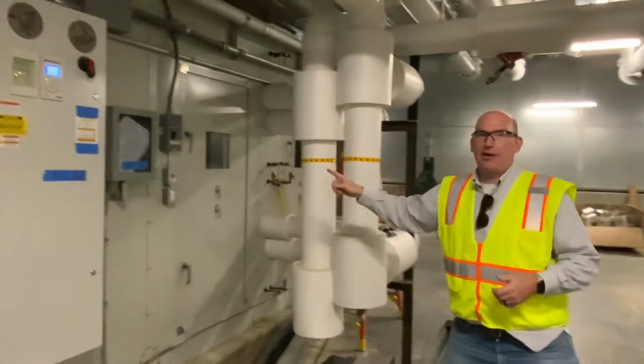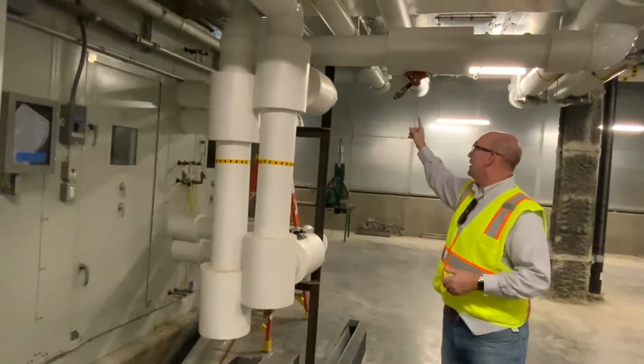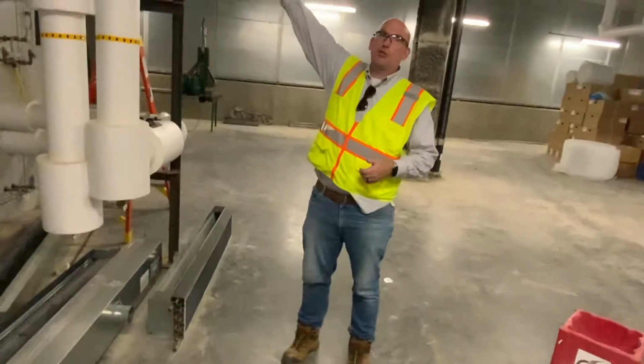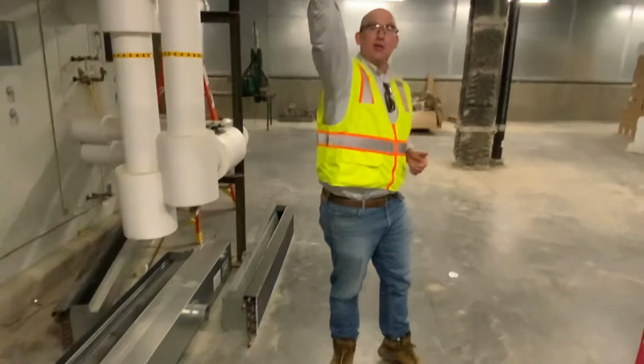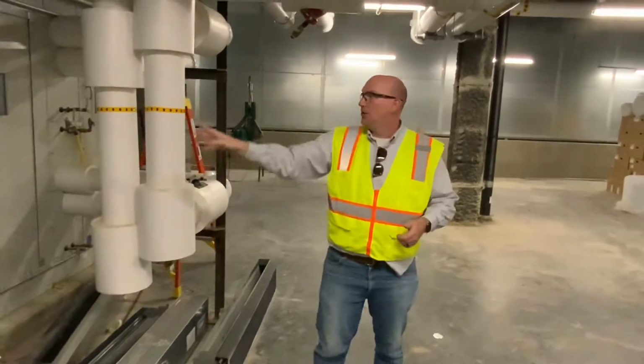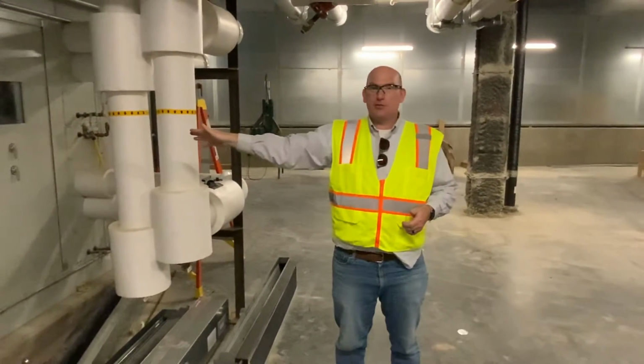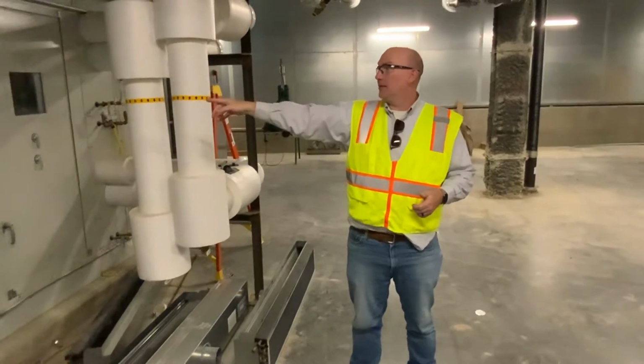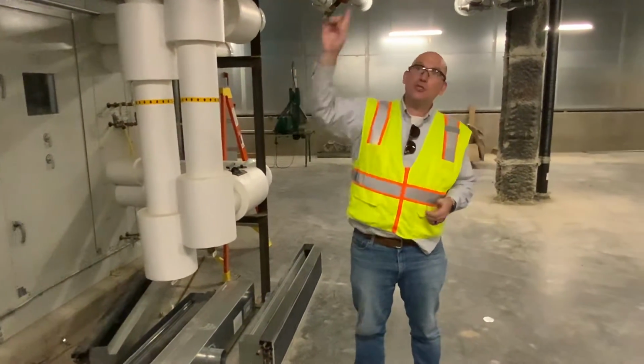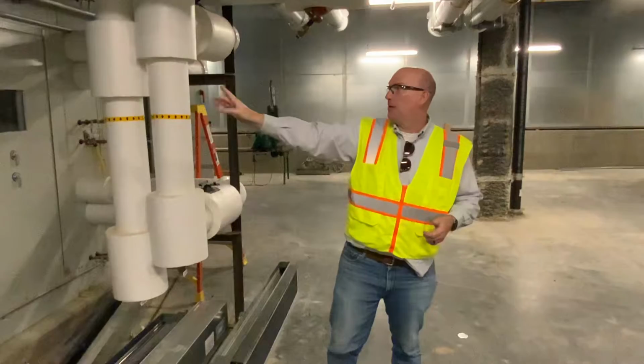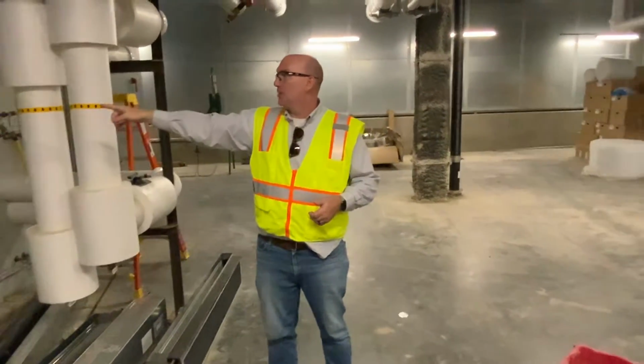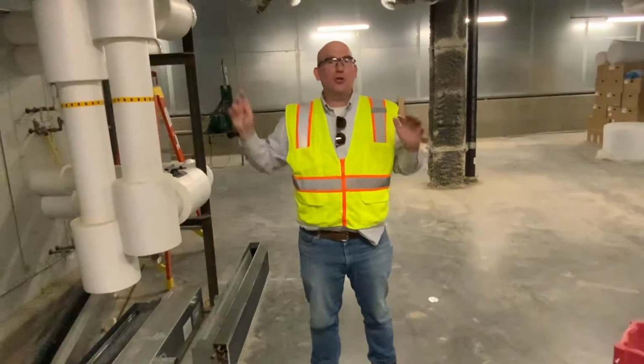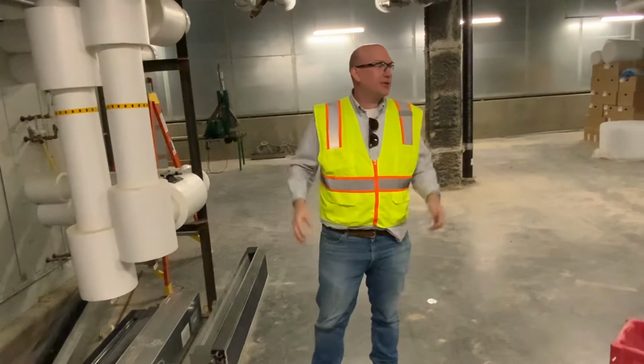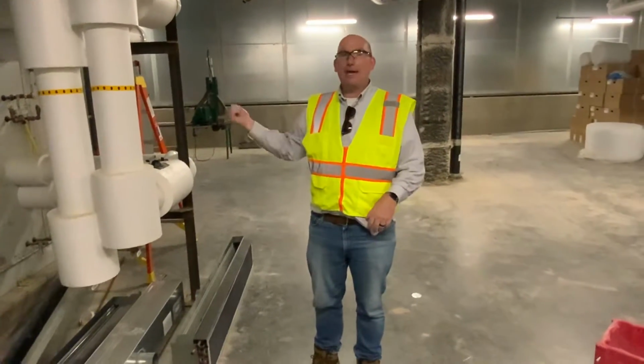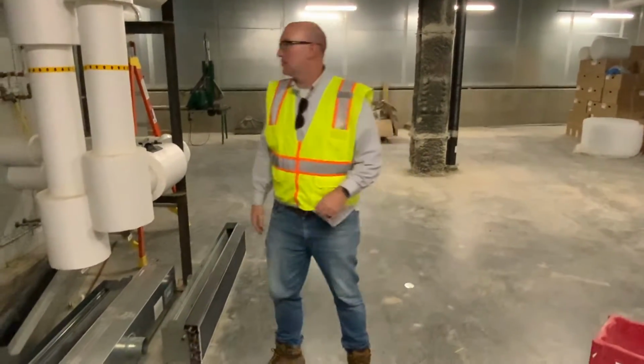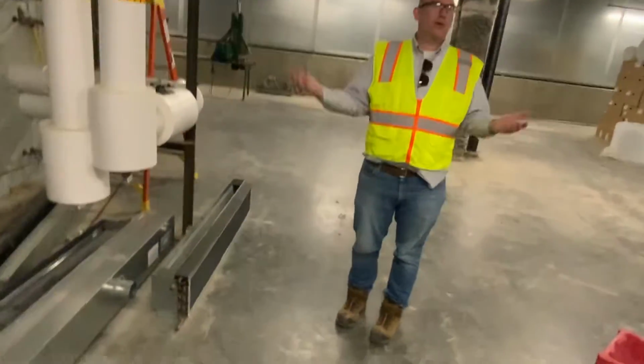We have an Ebtron airflow station in the discharge ductwork, the return ductwork. We have one in the exhaust ductwork and one in the OA. So that's belts and suspenders. So that's that thing sitting there, and I think we are using the ones for the exhaust. We're picking them up, and we are picking these up, but they're just monitoring. So you have a belt, okay, so belt and suspenders, but the Ebtrons are the ones we're actually controlling, right? Any other questions about the air handlers?